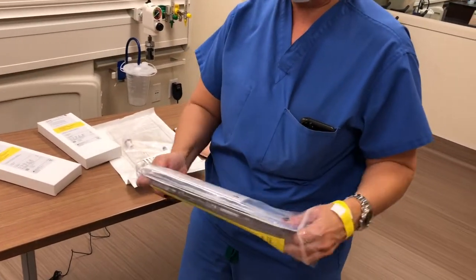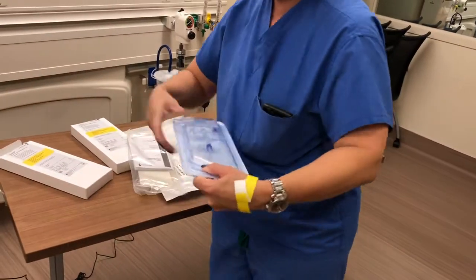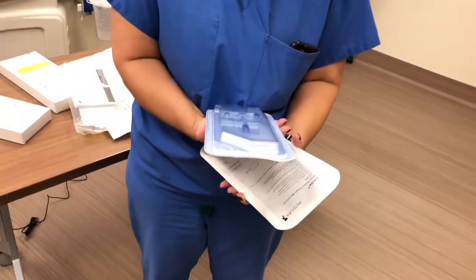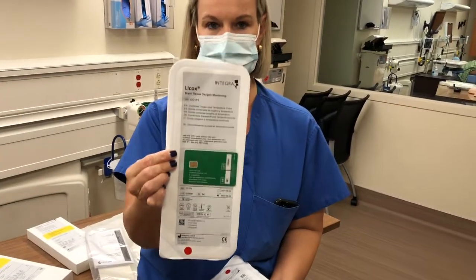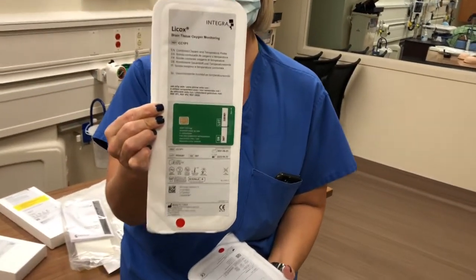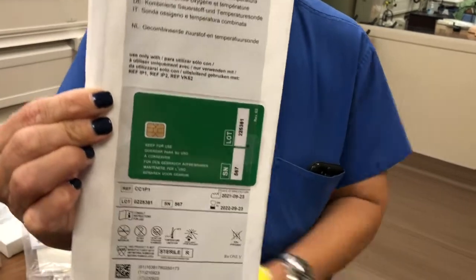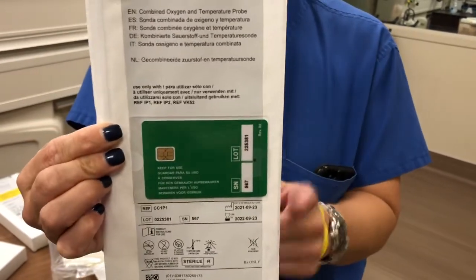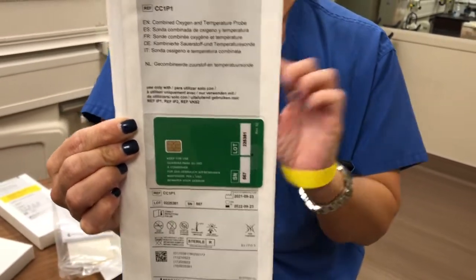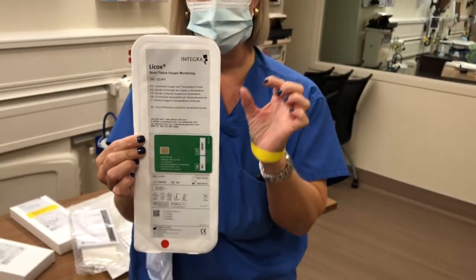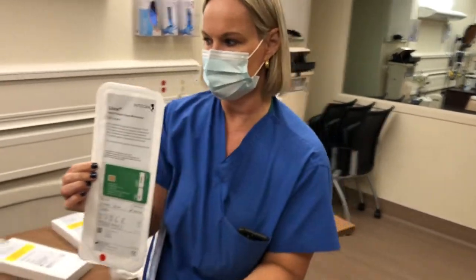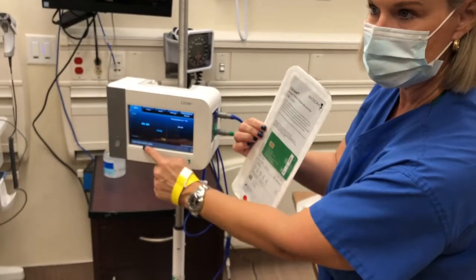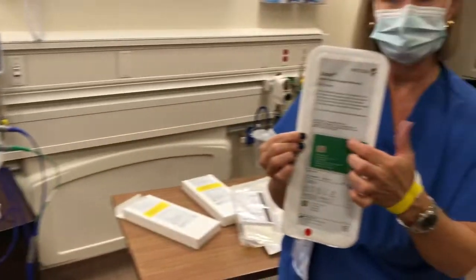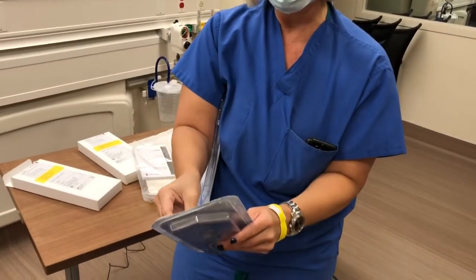And what happens here is you've got two active pieces here. One is the probe, which we call a CC1P1. Notice the green card that's here. This is the green smart card that is the actual factory calibration to the particular probe. It is literally stamped with the digit that it is. Like when I talked to you earlier about there being a probe number in the bottom right corner, that's this number.